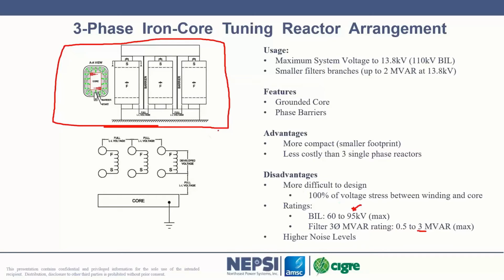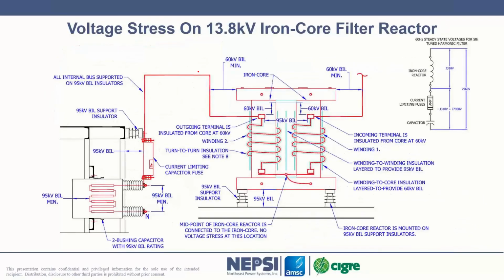Key difference between single phase and 3-phase reactors is the core is grounded in a 3-phase reactor design, and the voltage stress that now exists between the winding and the core is basically the line to neutral voltage of the system. So you have a continuous high voltage condition across the insulation system. In my opinion, the 3-phase reactor is a less reliable design.